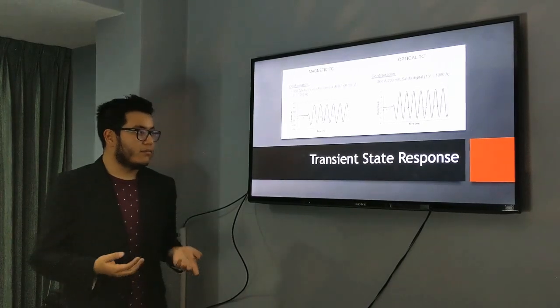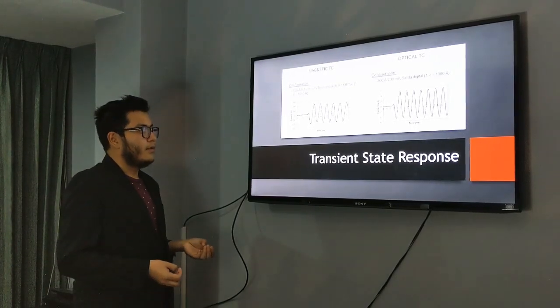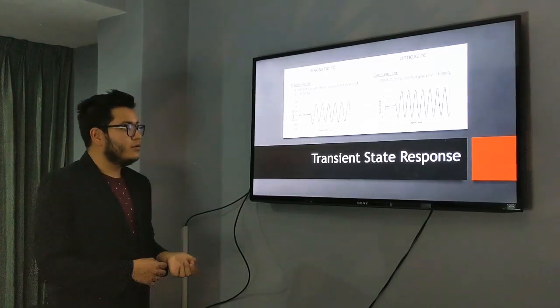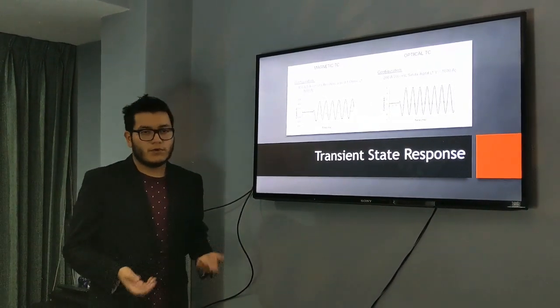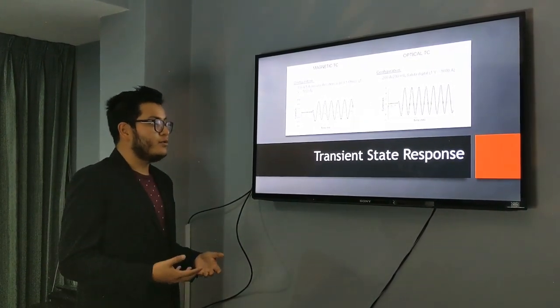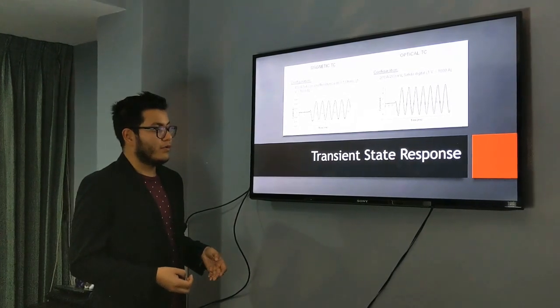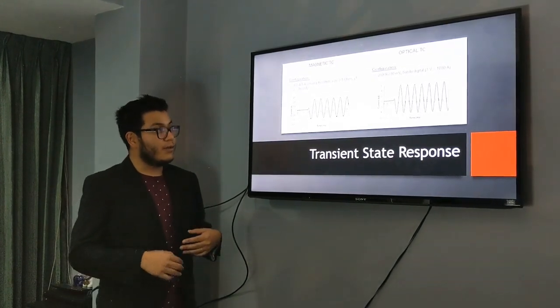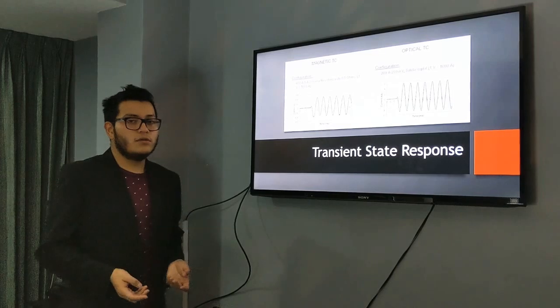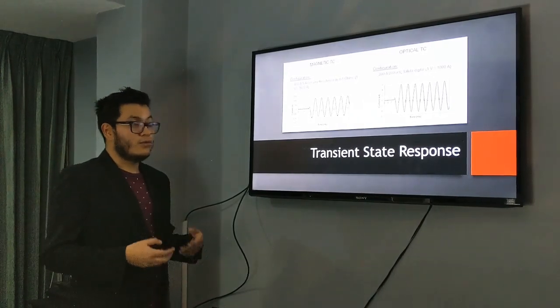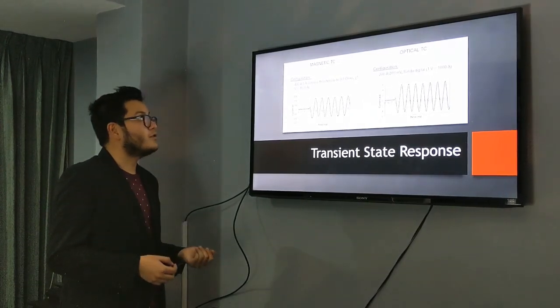So in the transient state response, the optical current transformer had a better response, where we can see that it reaches above its limit, and also it can handle much more current than a conventional current transformer.